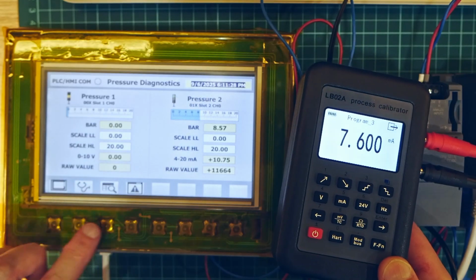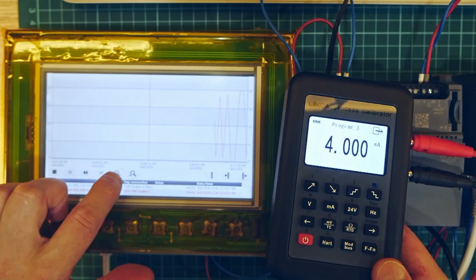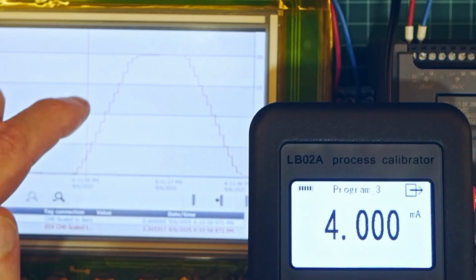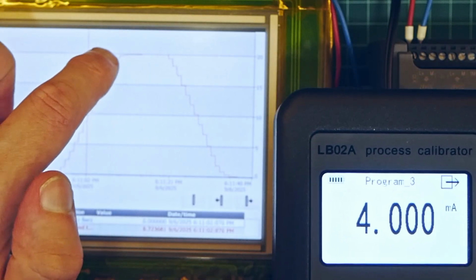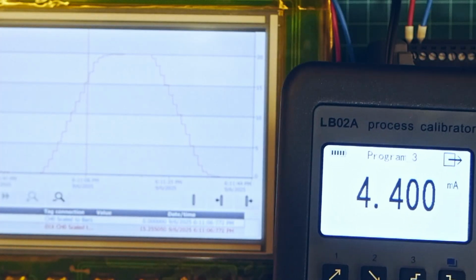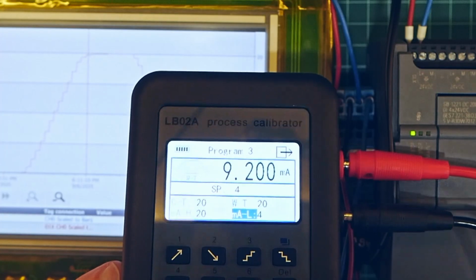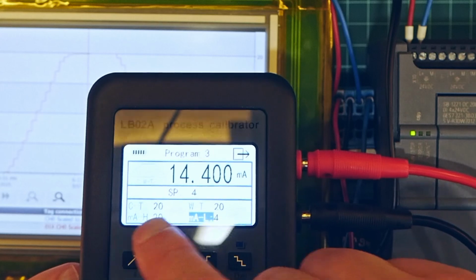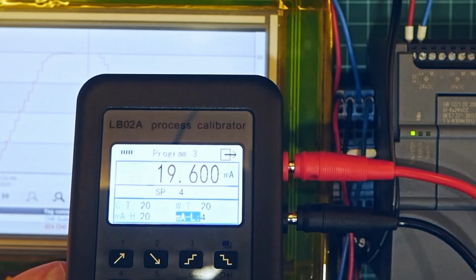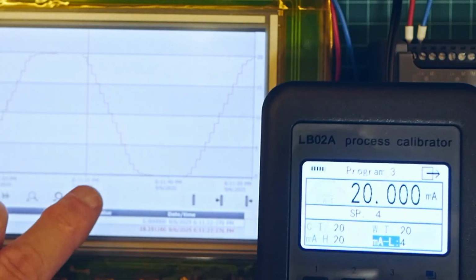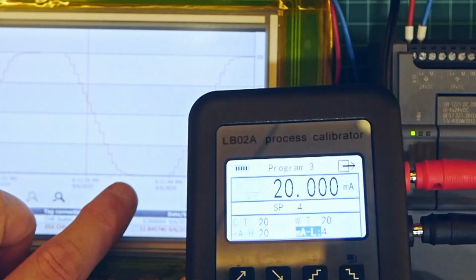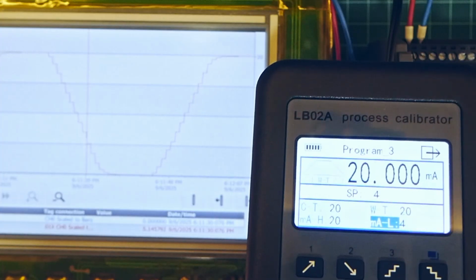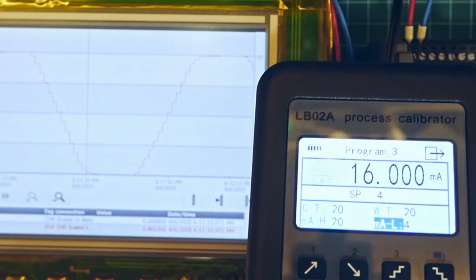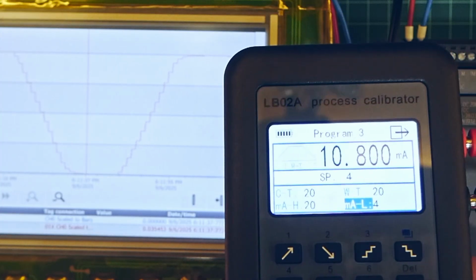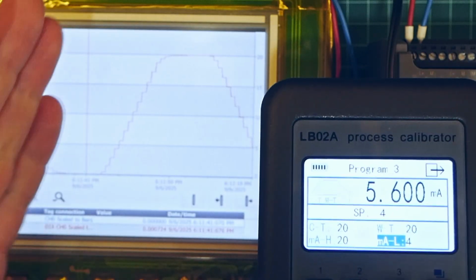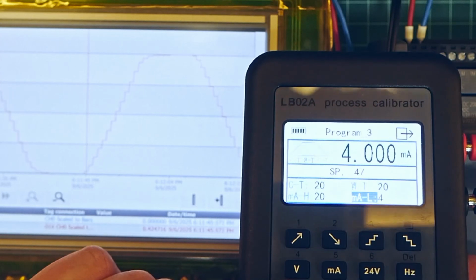Actually, we have trend here, so we can see how it actually works. As you can see, it goes ramp up to 20 bars. It's staying there. And then it drops. But again, it kind of has small issues, because this CT time is set to 20 and WT time also set to 20. But this doesn't correspond to reality, you know. When the high limit reached or low limit reached, it's actually staying there not 20 seconds, but more like 5. So these timers actually don't work properly, but still this sweeping could be useful.